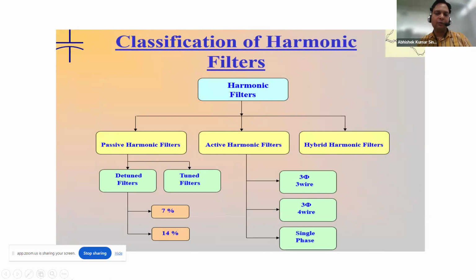For a tuned filter, we have to tune it according to the harmonics requirement. Whatever harmonics we want to suppress, we can tune to that, like the fifth harmonic, the seventh harmonic or the 11th harmonic. But in the case of a detuned filter, we need not have a harmonic study. We can plan it. If the harmonics are fifth or more, fifth, seventh or 11th, then we have to place a 7% detuned filter. If the harmonics in the system are third or more, then we have to place a 14% detuned filter.